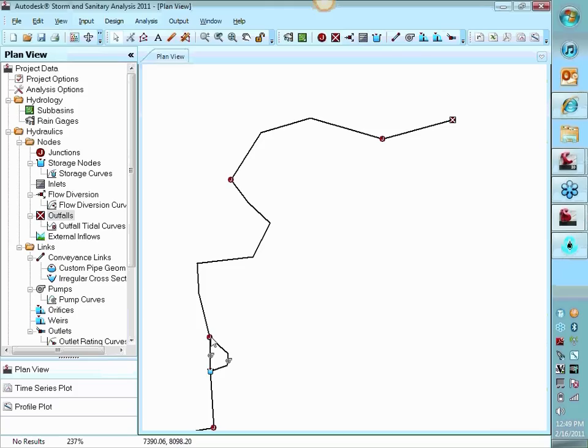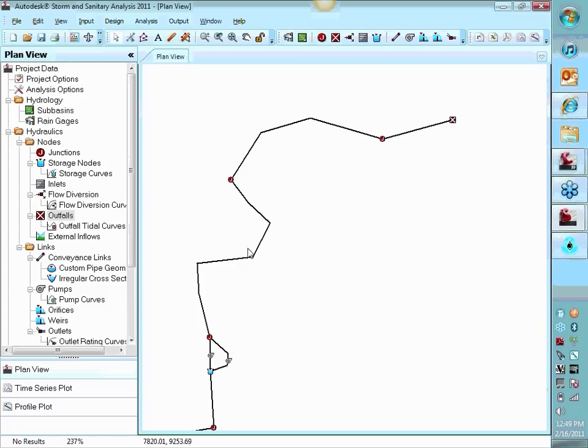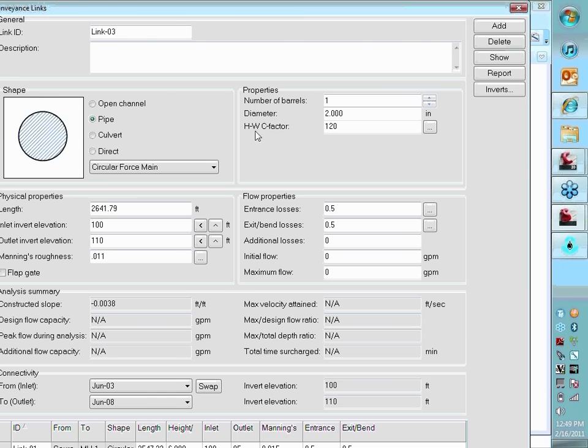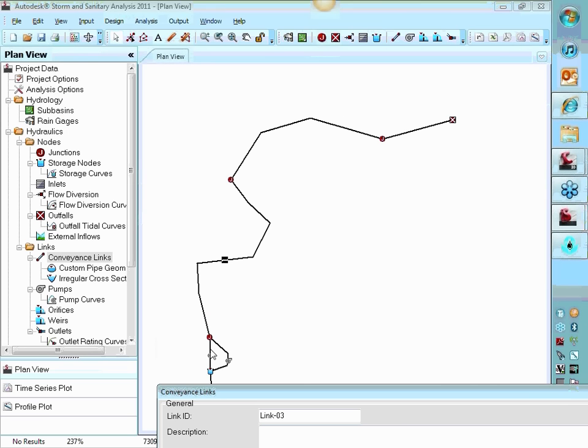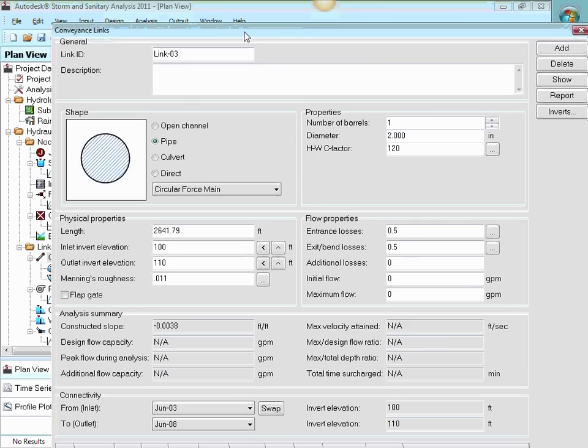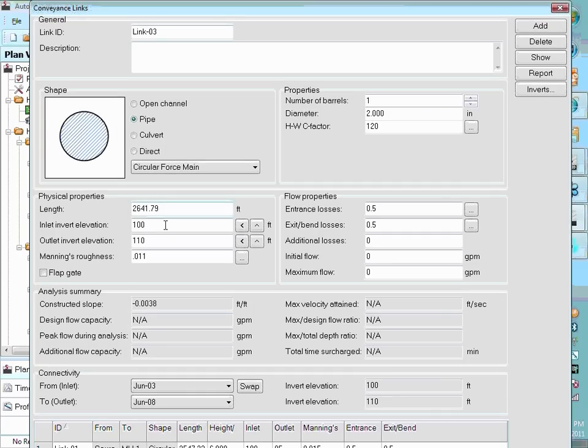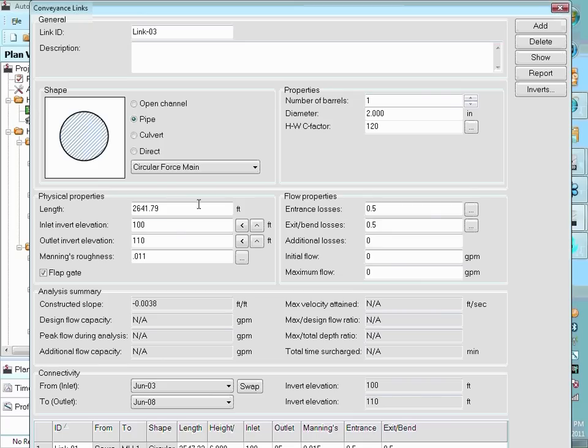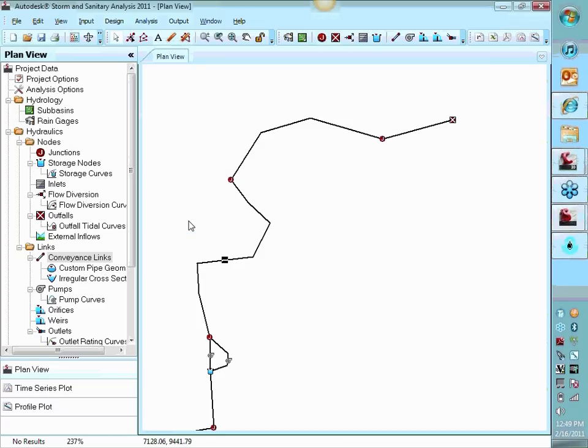One thing we do need to do on this pipe is how do we represent that there's a check valve in the system? So this flow when it's pumping up, it can't just flow back down into the wet well. If you double click on one of the pressure lines, so this would be the first line coming up. And you want to simulate a check valve in the system uses flap gate. You check that on. And that forces flow to go in one direction.